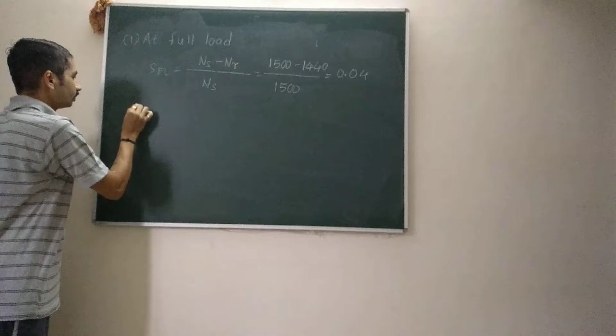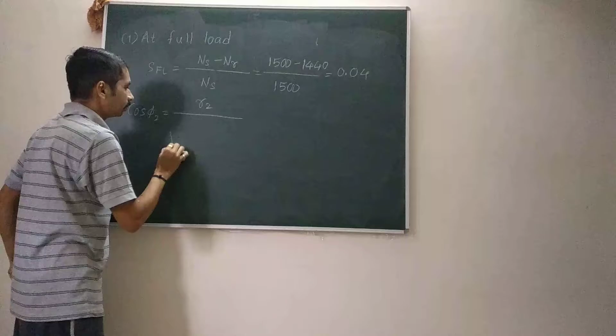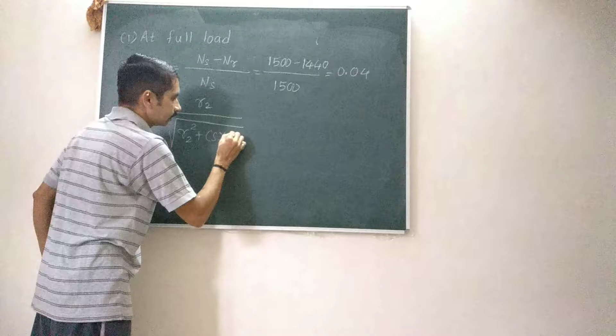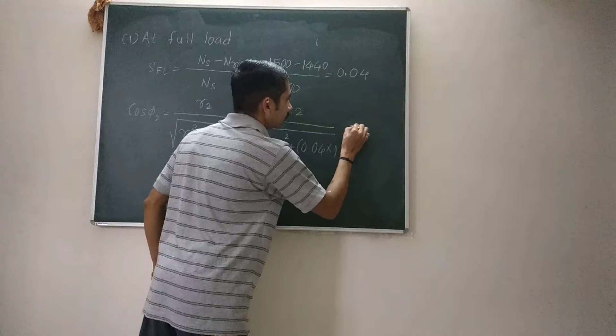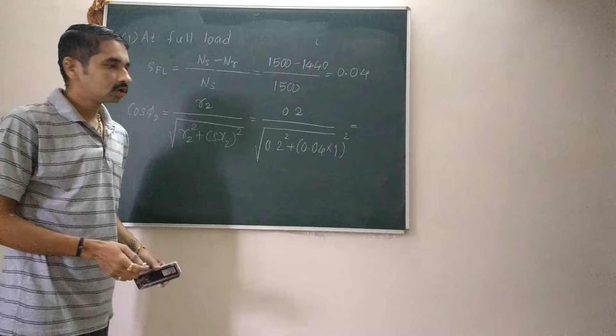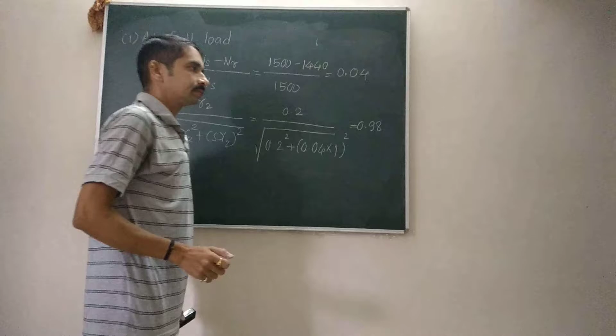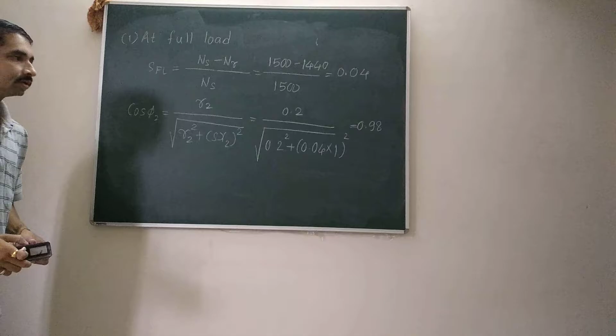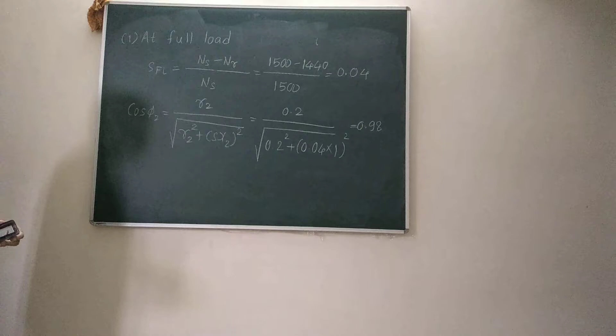So the rotor power factor at full load is given as cos phi 2 is equal to R2 upon square root of R2 square plus (sX2) bracket square. So it will be 0.2 upon square root of 0.2 square plus (0.04 into 1) whole bracket square. If I substitute the values, I am getting the power factor as 0.98. So this is the value of rotor power factor at full load condition. Please check whether you are getting the same answer or not. Okay, so is it clear up to this particular step?